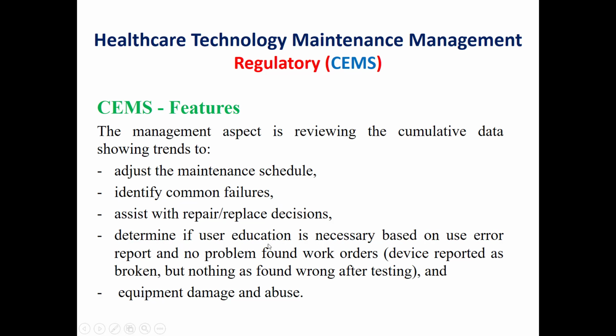Also, it helps determine if user education is necessary. This will be based on the user error reports and no problem found work orders. So an analysis of the work orders and the reason behind these work orders will help us to determine if the user education is necessary, based on the number of these work orders.